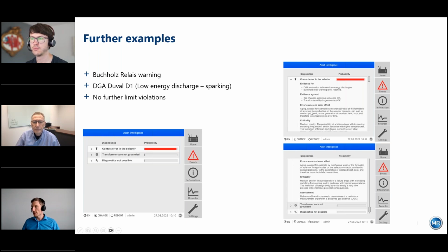You can still maintain the transformer in operation, but it's useful to make a DGA, to have an offline DGA in the laboratory, and also to make a vibroacoustic measurement on the selector in order to be sure what happened there.